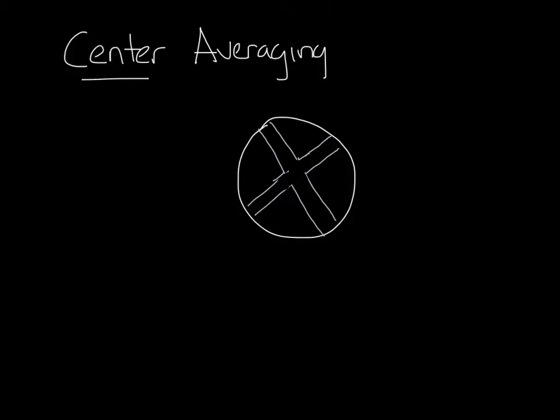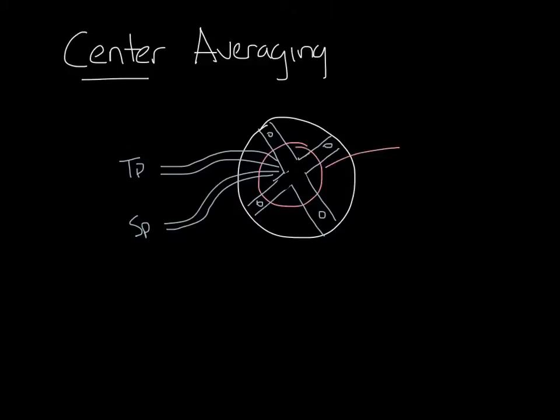Okay, so we are again looking into the inlet in the direction of airflow. You'd have holes here on the front that are measuring total pressure. There would be holes on the back measuring static pressure, but you can't see them in this drawing. Your pressure taps would come off here. Let's say the top one is reading total pressure and the bottom one is reading static pressure. Your reading is being taken at the center of the device, hence the name center averaging.